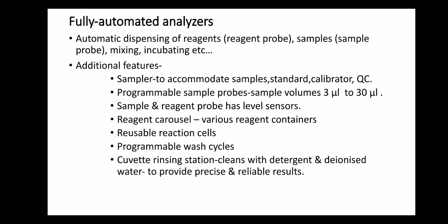Standard, why do we require? To check if the test is working properly. Calibrator: if there is any defect in the test results, any variation, or if we have doubt with the analyzer, we calibrate it once. That is done by calibrator. A solution is run in the instrument, and the calibrator has some values. If the instrument gives exactly that value in that range, then it is calibrated properly. Then we can go ahead with the processing of samples. If there is any defect in this calibration, again we call the biomedical engineers to sort out the issue.